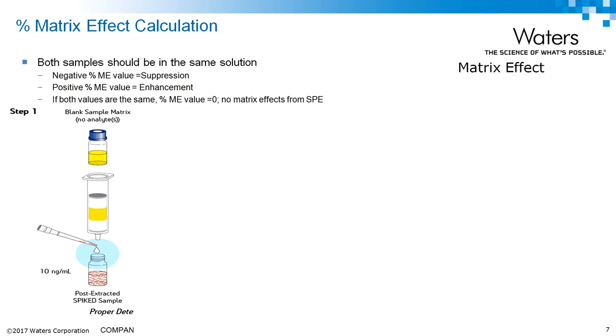The next calculation is equally as important: the matrix effect calculation. This will give you a sense of the specificity of your methodology and helps you characterize it so that you know where to place your efforts when you're looking to optimize. Here again, we're going to create two samples — one contains residual matrix, and the other is merely a solvent standard.